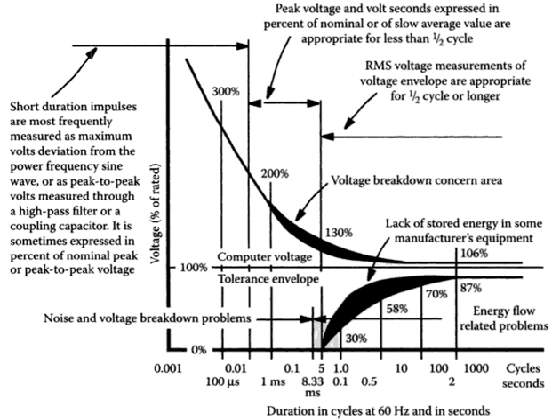Random or repetitive variations in the RMS voltage between 90 and 110% of nominal can produce a phenomenon known as flicker in lighting equipment. Flicker is rapid visible changes of light level. Definition of the characteristics of voltage fluctuations that produce objectionable light flicker has been the subject of ongoing research. Abrupt, very brief increases in voltage, called spikes, impulses, or surges, are generally caused by large inductive loads being turned off, or more severely by lightning. Undervoltage occurs when the nominal voltage drops below 90% for more than 1 minute.